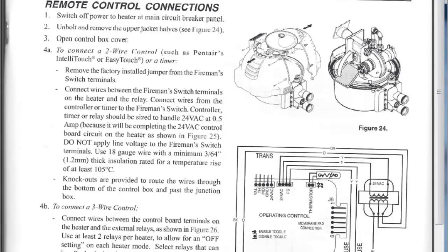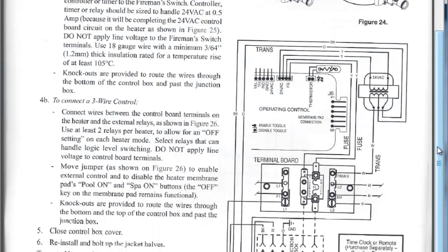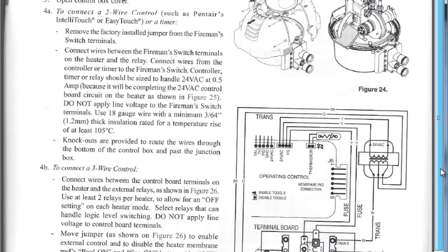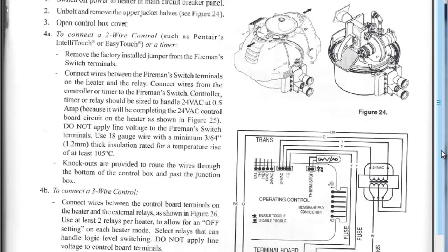Do not run your low voltage wiring through your high voltage—keep it away from your high voltage. And if you're connecting up to your fireman's switch, turn off the power first and keep that yellow jumper wire in the back corner for testing purposes. I hope that helps someone out there with a Sta-Rite heater.